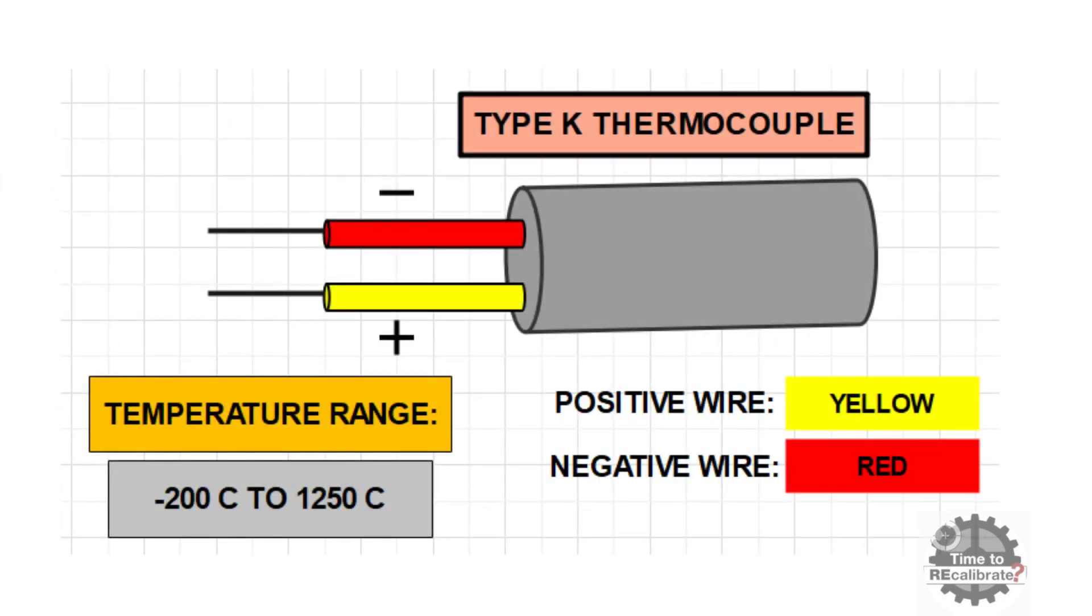As you can see, second type is K type thermocouple. K type thermocouple has yellow and red wire combination. In this combination, yellow wire is positive and red wire is negative. And K type thermocouple has temperature range of minus 200 Celsius to 1250 Celsius.